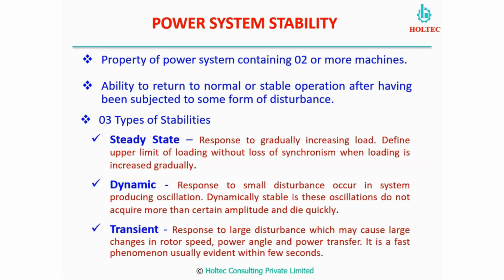We normally divide the studies into 3 types: steady state stability, dynamic stability and transient stability. Steady state stability is basically normal operation, when we increase or decrease the load at predefined intervals, or do it gradually, without losing synchronism in the system. So when we have multiple sources operating and we change the loading on any source or any load, the system should not lose synchronism. This is during normal operation, so we tune our system in such a way that it can withstand these variations when we change the loads.